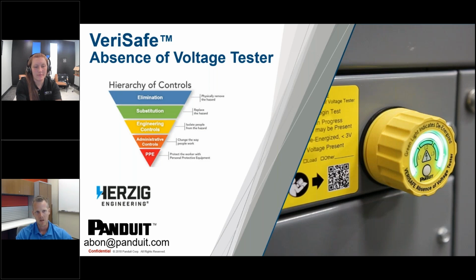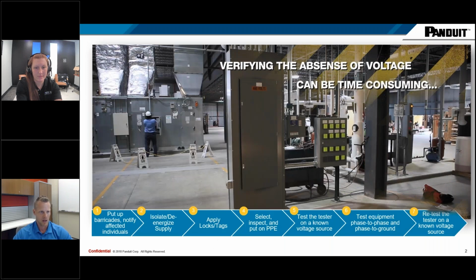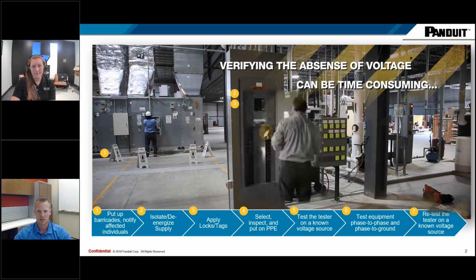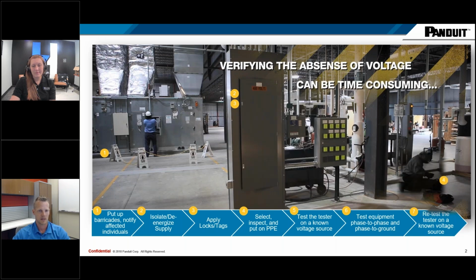So getting into the process real quick, like I mentioned: putting up the barricades, notifying affected individuals, folks nearby, that you're going to be opening this panel that might have hazardous energy in it. Determine all sources. Disconnect the breakers, go through and apply your locks and tags, putting in your PPE, selecting it, inspecting it, and so on.